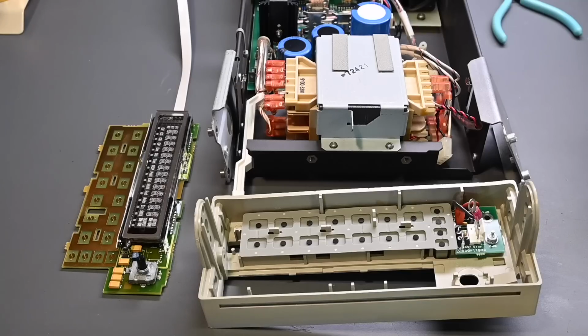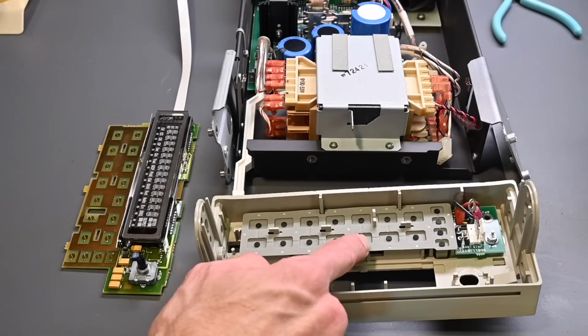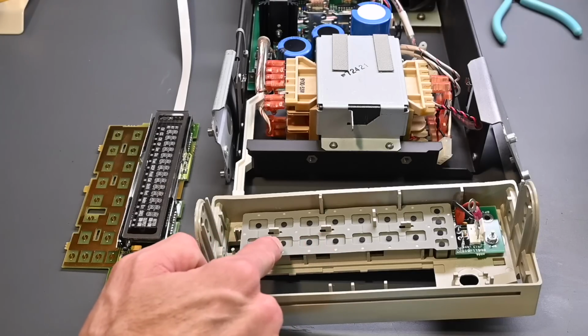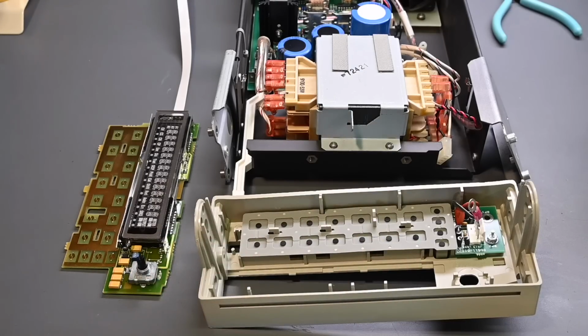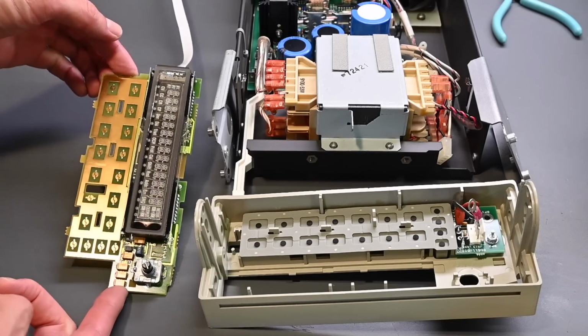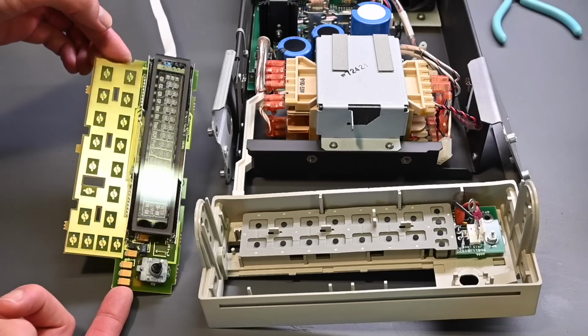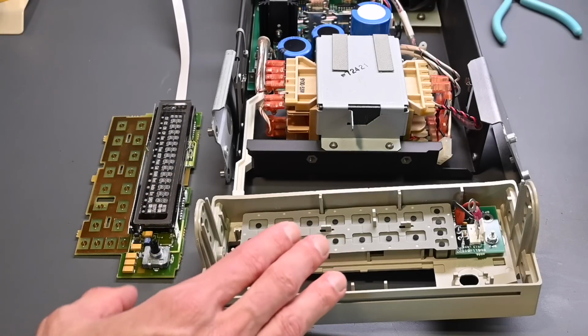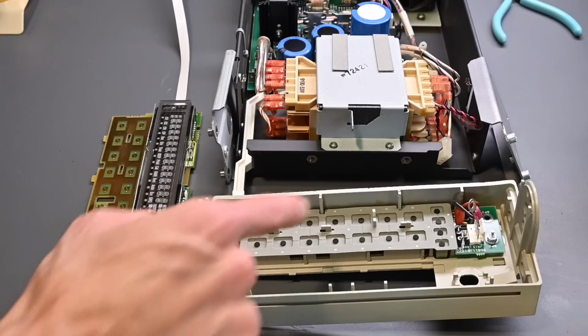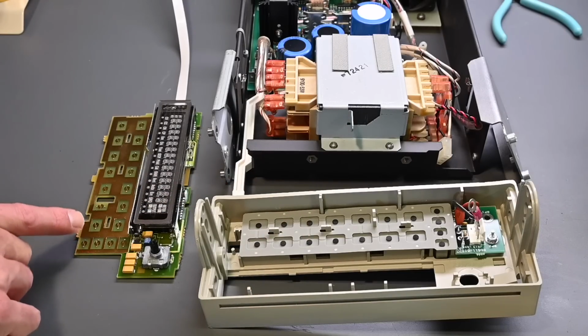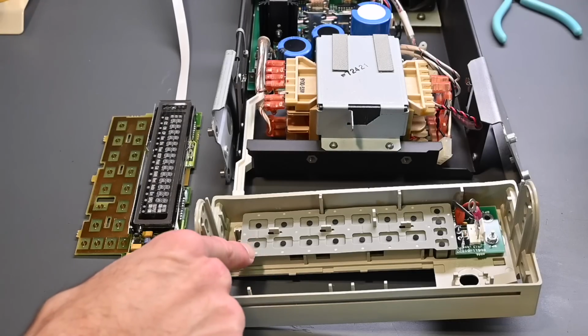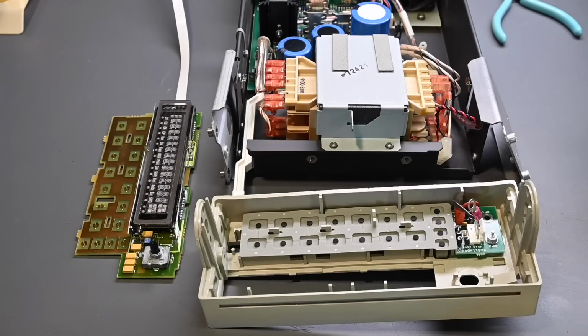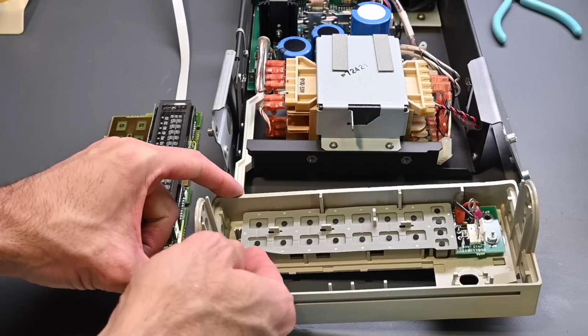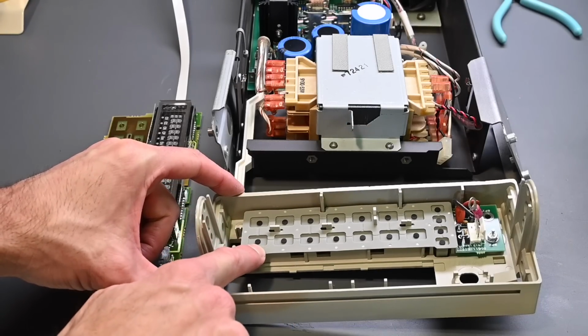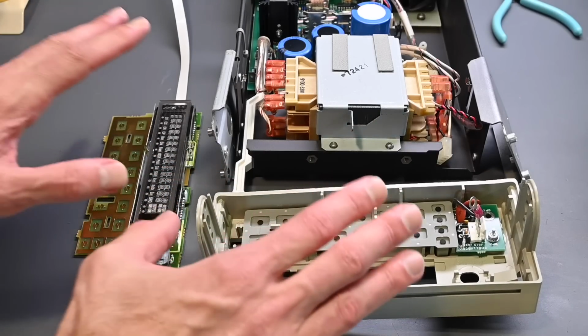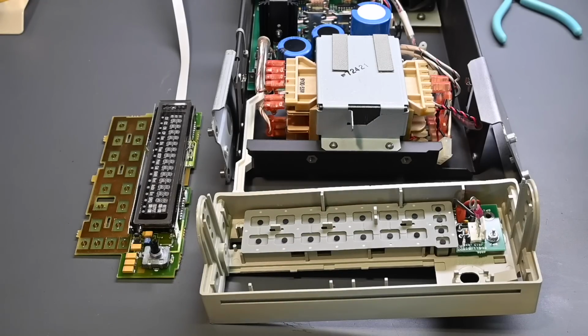And on the keypad right here, you never want to clean these carbon contacts, those little black round dots that are on there. You don't want to mess with those, but it's perfectly fine, again, to clean the contacts that are on this circuit board over here. If these keypads ever get intermittent or you have to press the button numerous times, usually it's just because the contacts are dirty on the board, but sometimes the keypad itself can actually wear out. And if you have to change the keypad, it just fits in here. You can see how that corner lifts up right there. So they're very easy to change as well. All right, so I'll get everything reassembled, and then we'll continue on with the calibration.